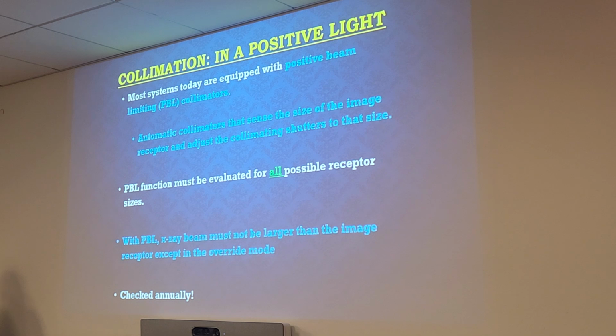For PBL, positive beam limiting collimators, that's basically your automatic collimators on your X-ray machine. So when you put those detectors inside of the table and you hear the machine make that noise, zip, zip, zip, zip, it's automatically collimated. Okay? So that's what PBL is. And the X-ray beam from PBL should not extend past the IR unless you put it in override mode. So what is override mode? That's the key, right?